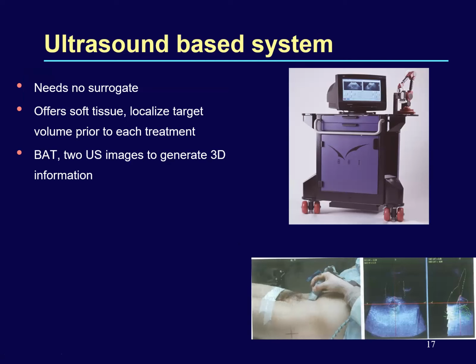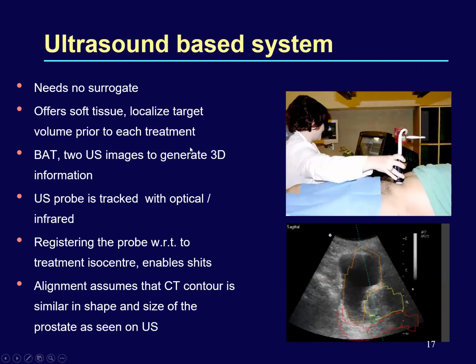The next one is the ultrasound guided system. The ultrasound guided system has the advantage that it does not require a surrogate, because it offers soft tissue information, which is good to localize every day prior to the treatment. So ultrasound probes were tagged with optical infrared markers to give a room isocenter with respect to the treatment isocenter, and they enabled us to do shifts of the table to match and reproduce the target.